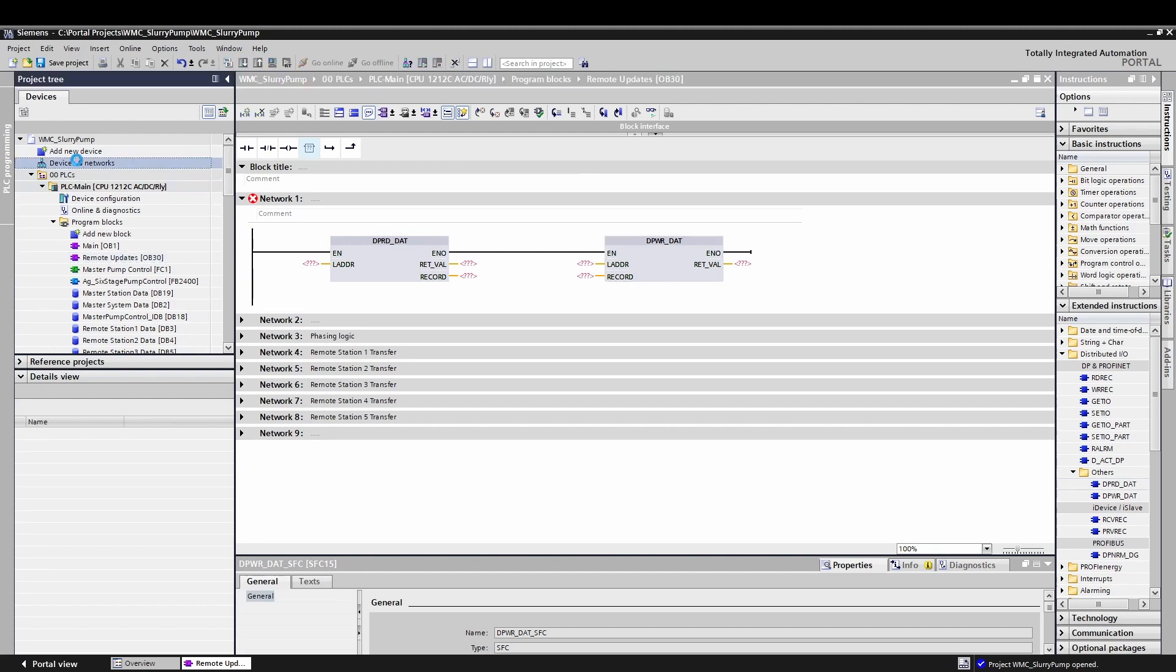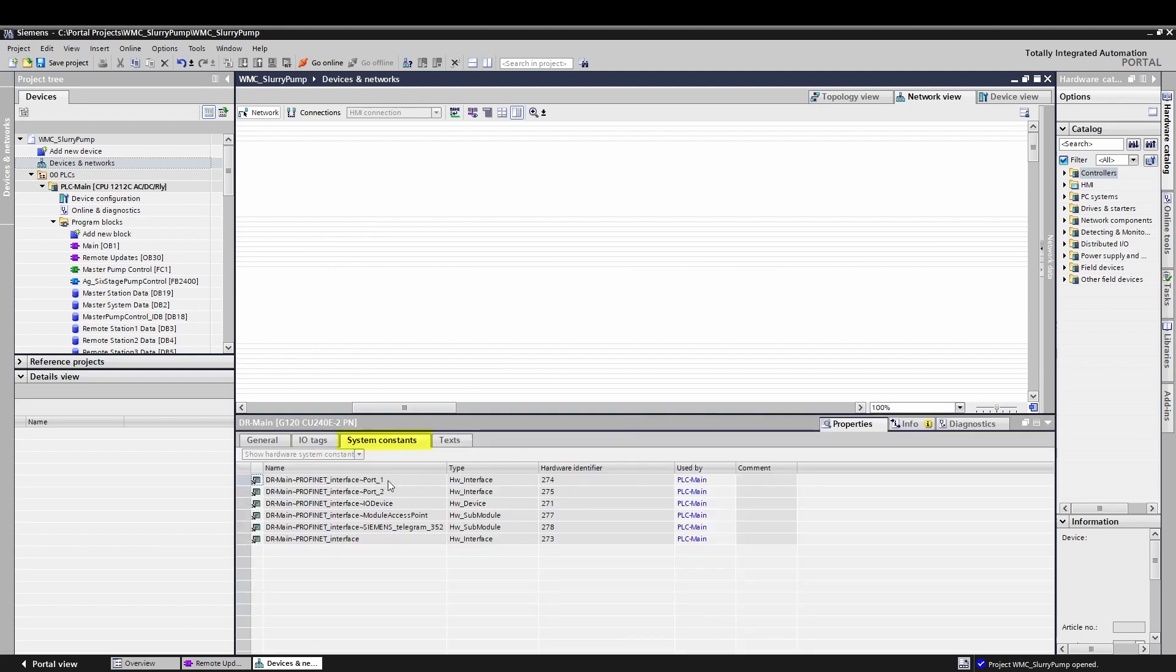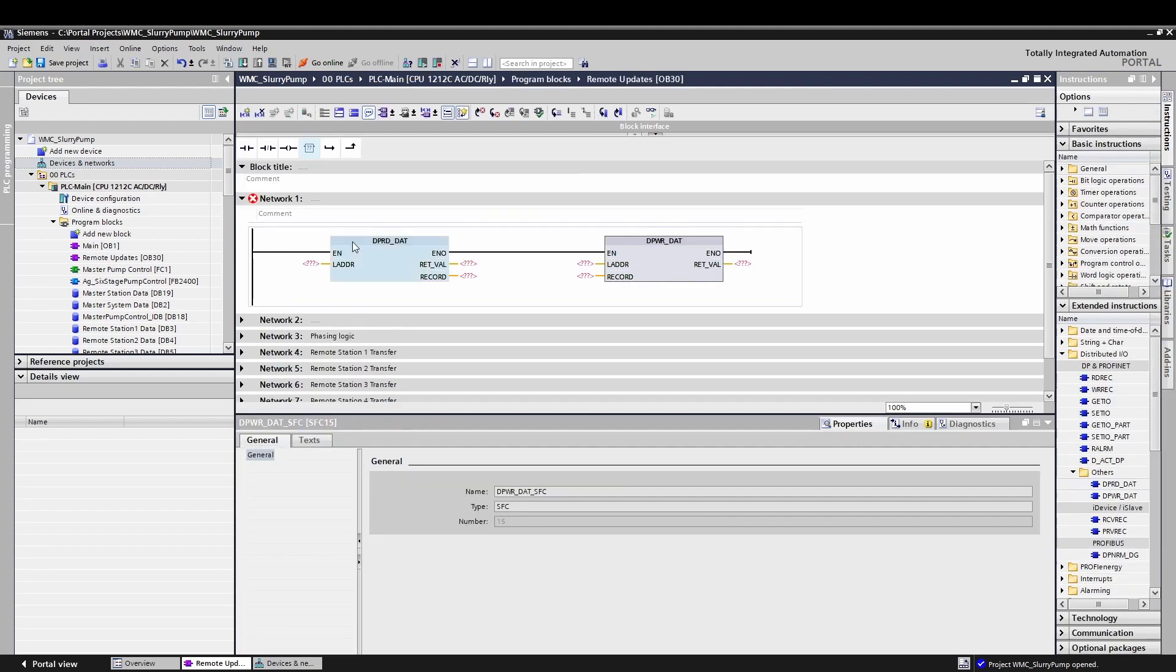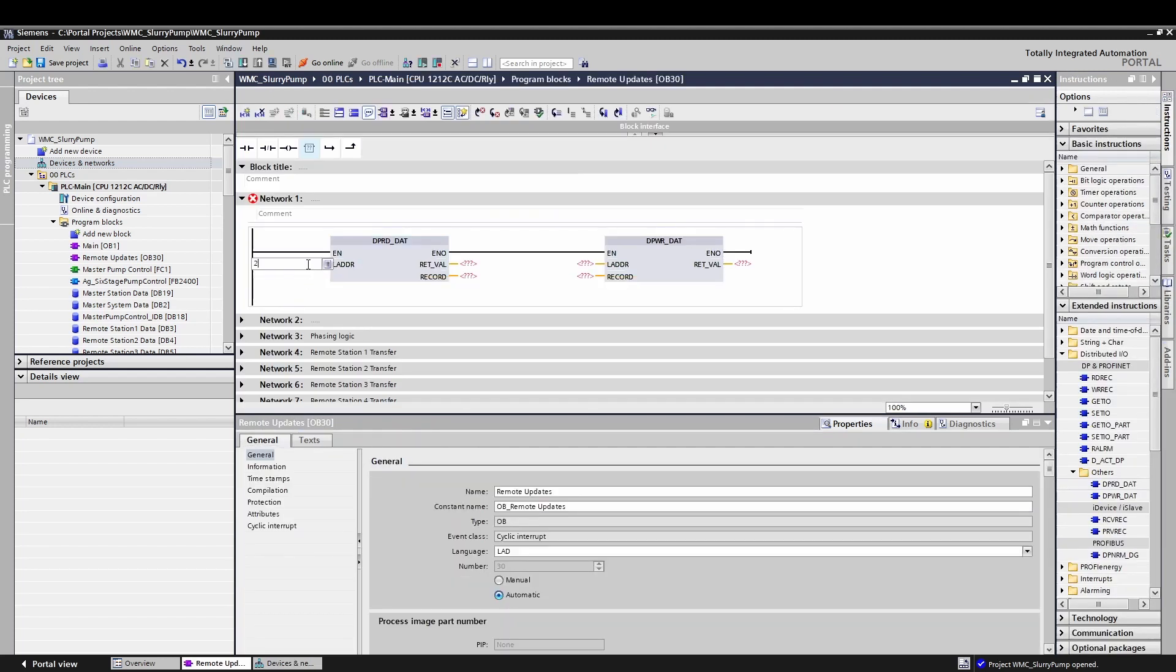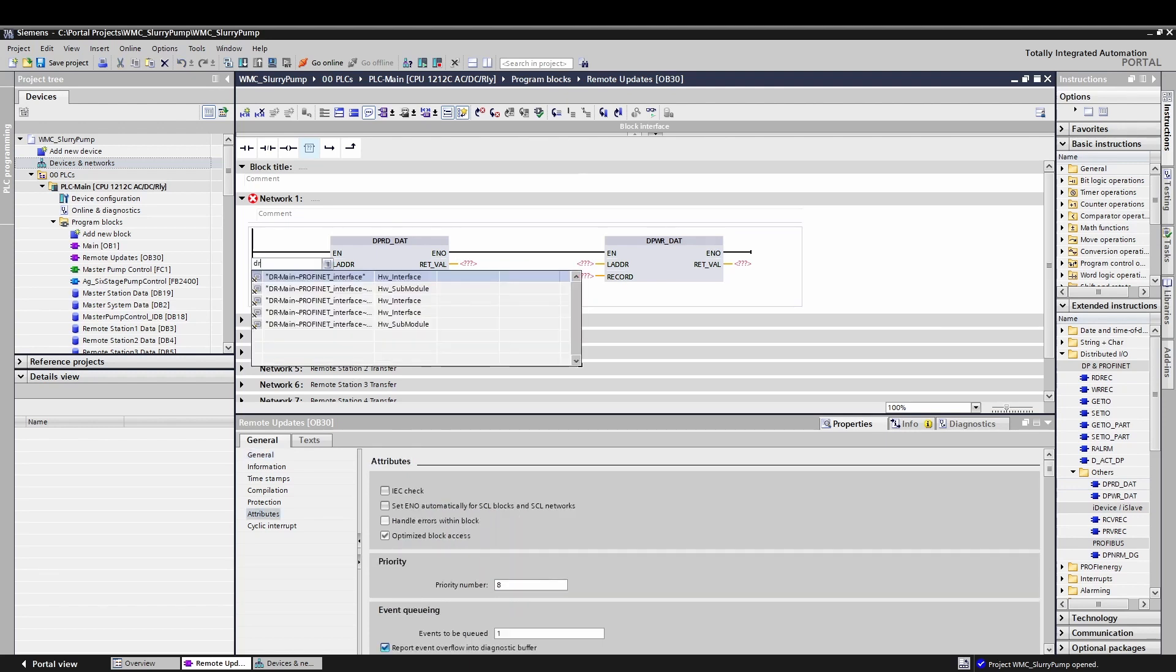For both blocks in Portal, the L address parameter is the hardware ID of the device you're trying to communicate with. To find the hardware ID of a device, find it in the network view of the device and networks page, and click on the device, click in the inspector window. Under the properties tab, find the system constant sub tab and select hardware submodule of the telegram if it's a drive or the module access point if it is another external device. In your code, you can enter this hardware identifier a couple of different ways. You can directly type in the number found in the section beforehand, but it doesn't give you any information about what you're communicating to.